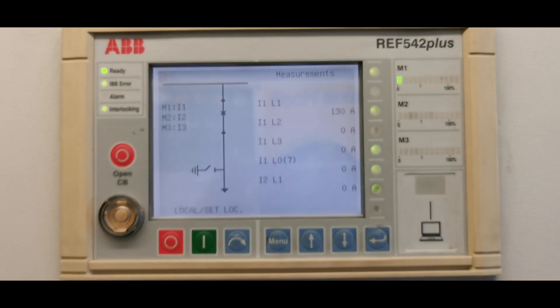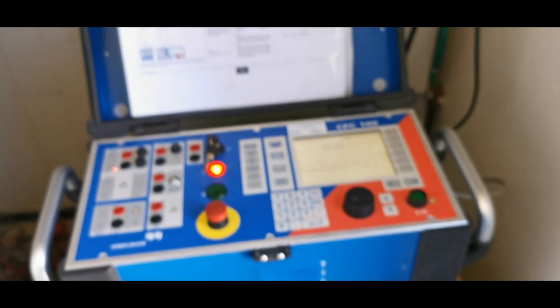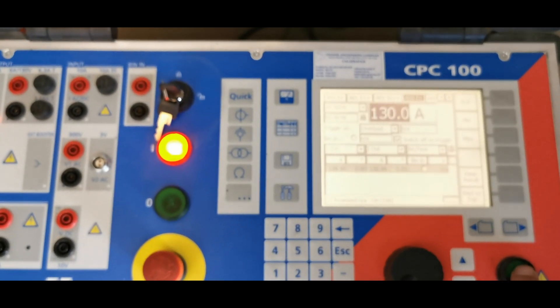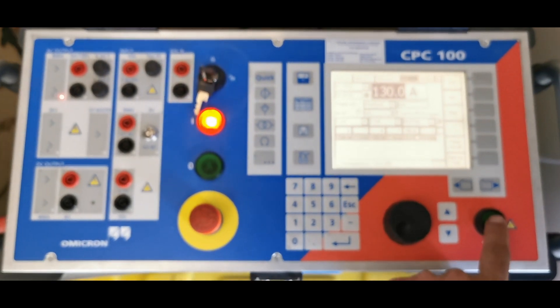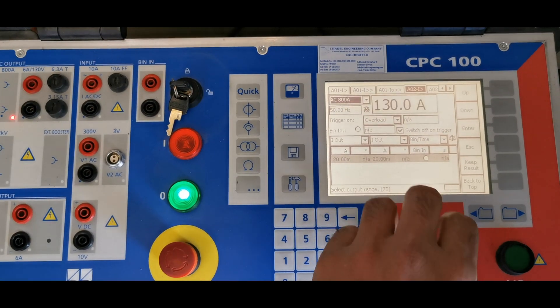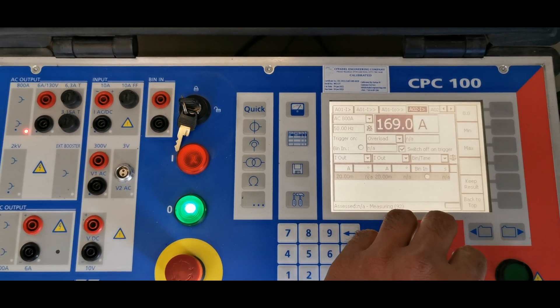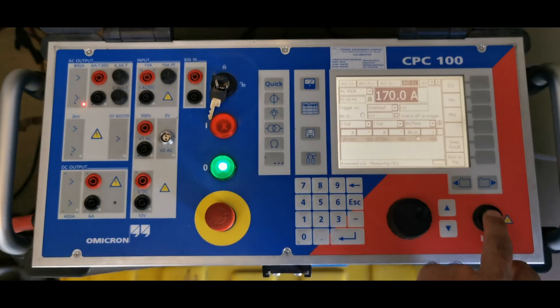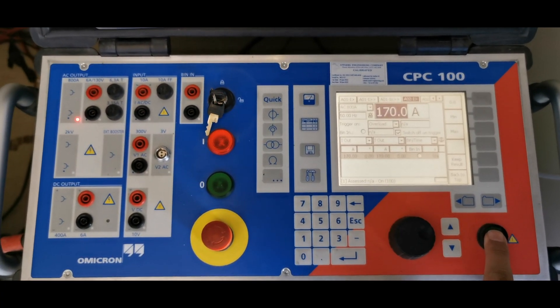Step 5: Checking relay and breaker response on REF542plus HMI. Using the REF542plus HMI to verify test results: navigate to the main screen and check breaker status — open or closed. Go to the protection menu and verify trip signal activation. Check the event log for trip details including fault current value, trip time, and protection function activated, for example overcurrent or earth fault. If the breaker did not trip, verify CT polarity and secondary wiring, relay trip settings such as overcurrent thresholds or delays, and breaker trip coil operation.